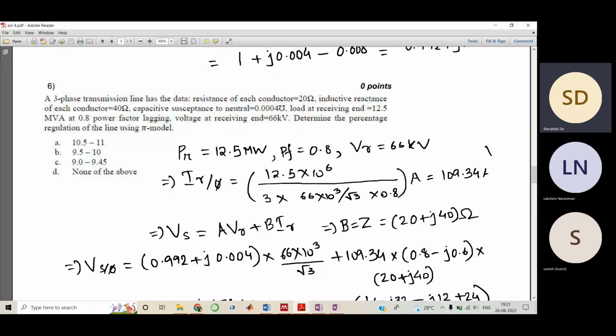And here there won't be any power factor used, right? Since this is 12.5 MVA, and this would be MVA only, I per phase would be MVA divided by the per phase voltage. There won't be any power factor involved.